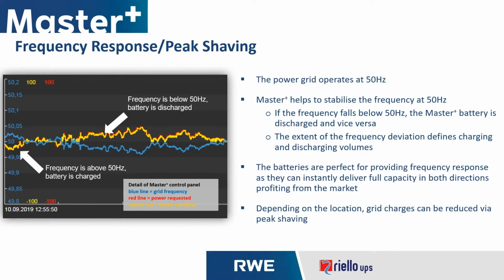Now the benefit of batteries is that they are perfect for providing frequency response, as they can deliver power instantly from full capacity in both directions and therefore profit from these markets. Now depending on the location, grid charges can be reduced via peak shaving. Now if we look at the image on the left hand side, we can see that the blue line represents the grid frequency, the red line represents the power requested, and the yellow line represents the power provided.